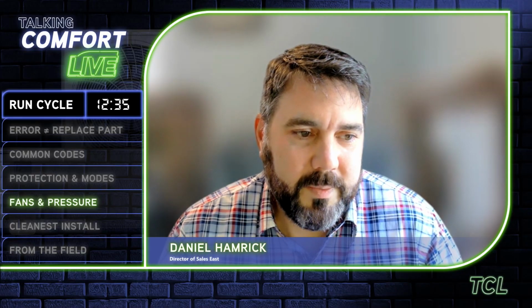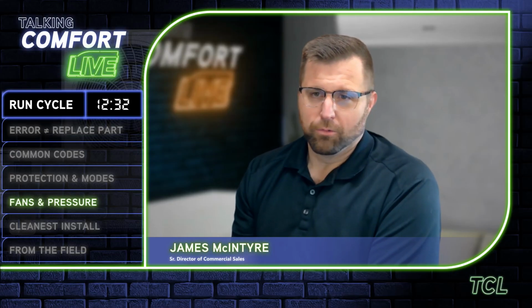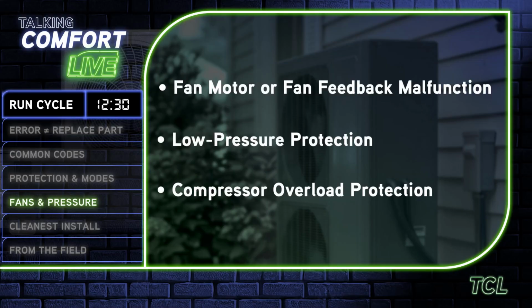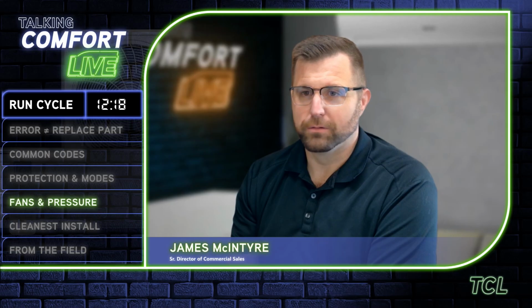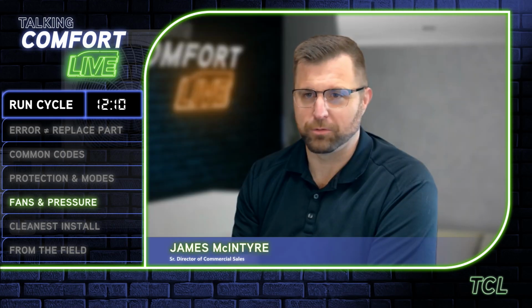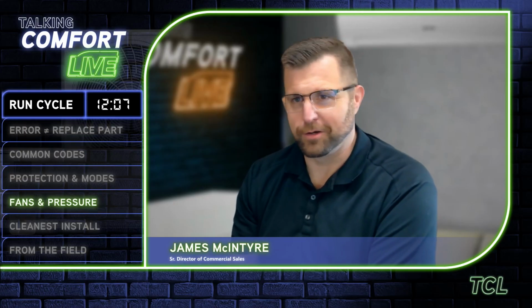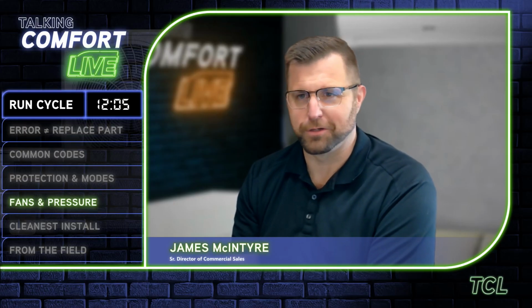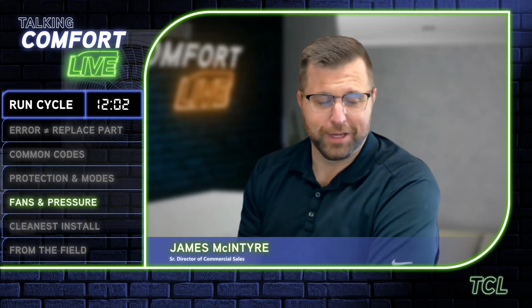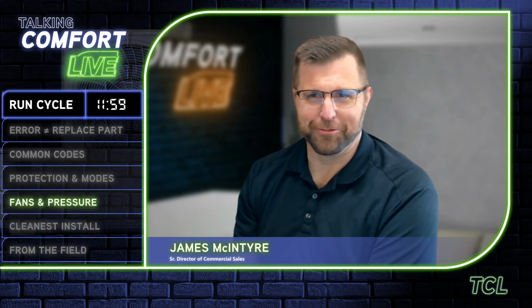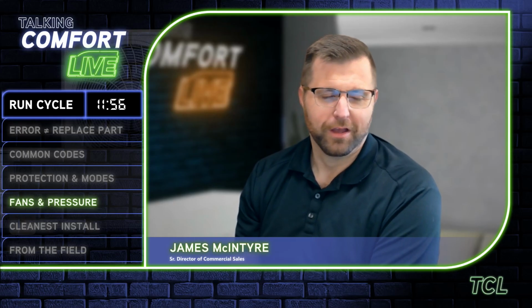So, low pressure protection. What causes us to have low pressure? Good question. The same thing on every system, isn't it? I mean, I got poor airflow. I could have a restriction. A refrigerant leak. Got to have refrigerant. As far as I know, I keep seeing these new engineers coming out with these refrigerant-less units and all that. I see articles posted about it, like Pro Talk and a handful of other groups on social media. But they're a long way away from implementation on something like that. But yeah, you got to have refrigerant.